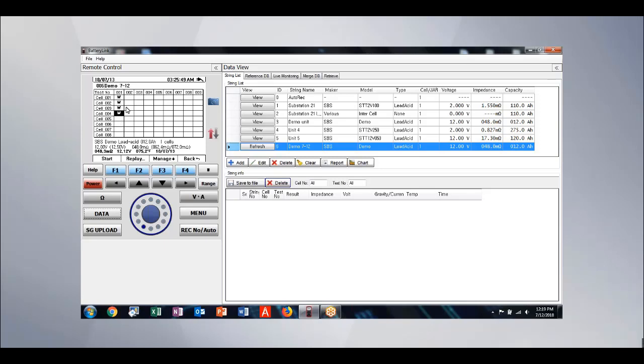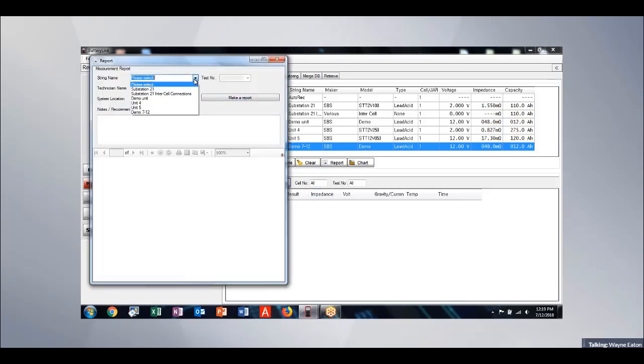So once I get all my readings from my string, reporting on the SBS-6500 becomes very easy. I simply click report. I go to that location that I want to generate a report for. If I have more than one historical test for that string, each one of those tests is going to be listed in that drop-down box. So test 1, test 10, test 56. Since I only have one here, there's nothing there, but I can just hit make a report.